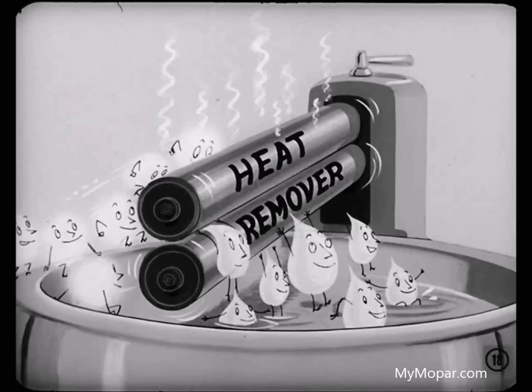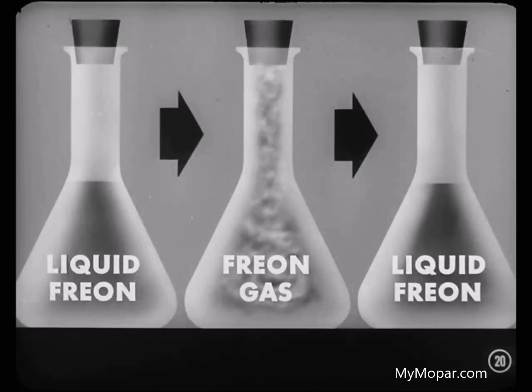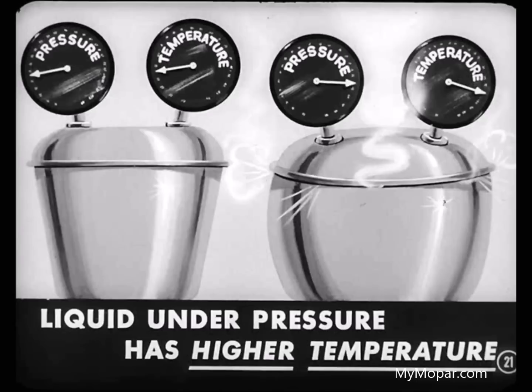But why compress it at all if it's colder as a gas? Well, that's a good question, Bill. When it's a gas, it has absorbed some heat, and we have to take that heat out so we can use the Freon over again to absorb more heat. So we put it under pressure and then remove the heat, which changes it back to a liquid. Then we can use the Freon again. By being able to change Freon from a liquid to a gas and back to a liquid, we can control the point at which it evaporates, and that's the point at which it absorbs the most heat. Remember: when you put a liquid under pressure, you raise the temperature at which it will turn to a gas.